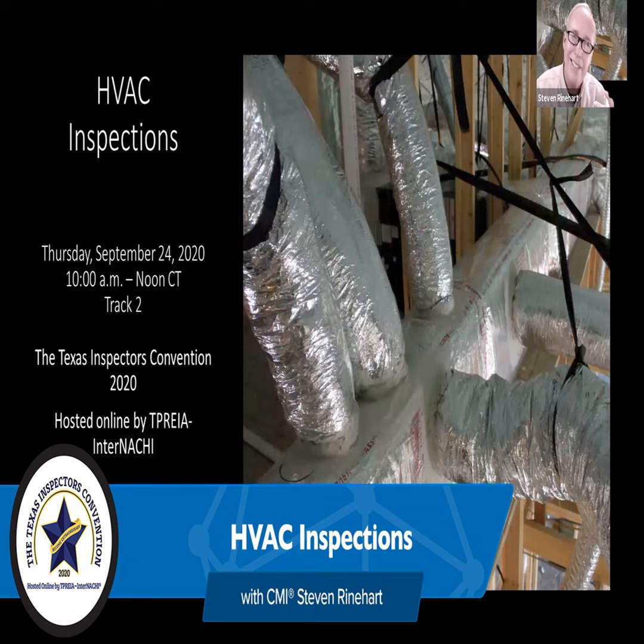So for whatever reason, it just didn't work. And we're not talking ductwork. We're not talking, like I say, no electricity or anything. It just didn't work for whatever reason. It didn't start up. If it's an electric, this is for all heating equipment. So if it's electric strip heat and it didn't produce any heat, that's easy. What if it only produced a little heat? You know, it's got a sequencer that'll turn on the strips one at a time, depending on your demand. Maybe it only turned on one strip, and you notice you only have maybe a 15-degree heat rise.